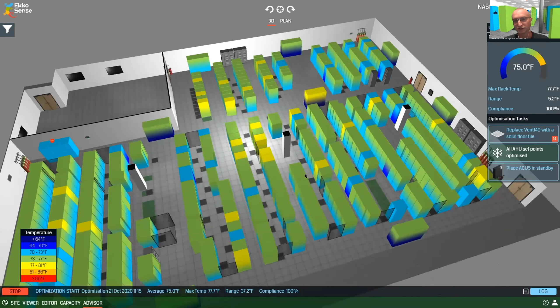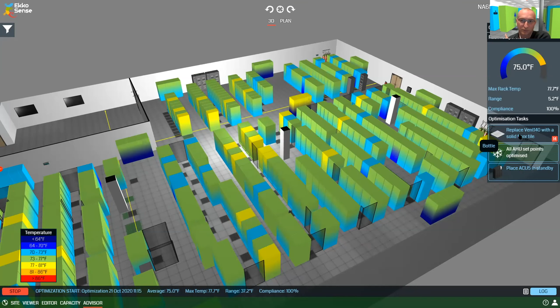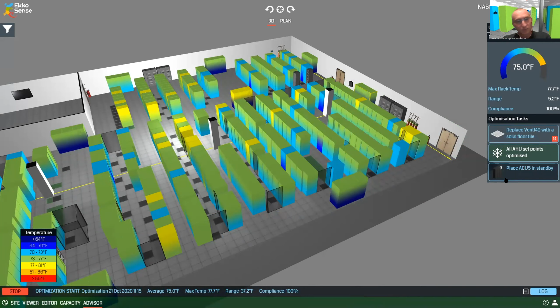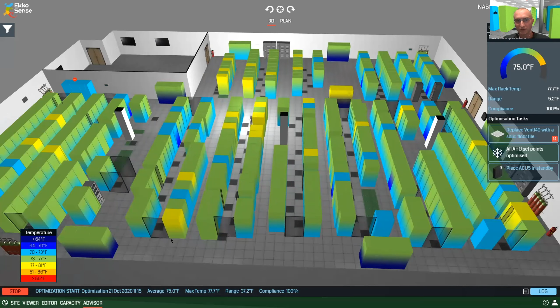And after it's had a bit of a think about the layout in here, it will suggest whether there are any floor tiles, for example, that might need changing. So you can replace floor tiles or open floor tiles or move them around. It also considers the AHU set points and whether there are any set point adjustments that should be made, or whether any AHUs need to be or could be put into standby, or, as I said, scheduling, you know, hot standby or cold standby options. So that's a quick route through some of the thermal and cooling capabilities that are within the software.